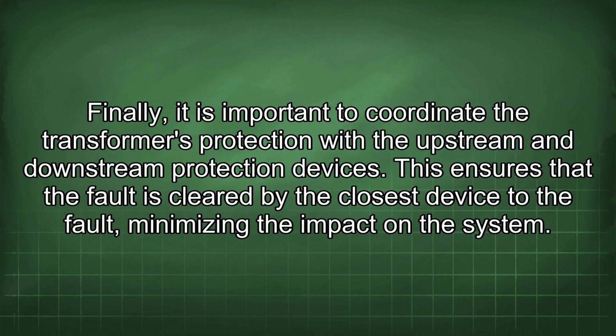Finally, it is important to coordinate the transformer's protection with the upstream and downstream protection devices. This ensures that the fault is cleared by the closest device to the fault, minimizing the impact on the system.